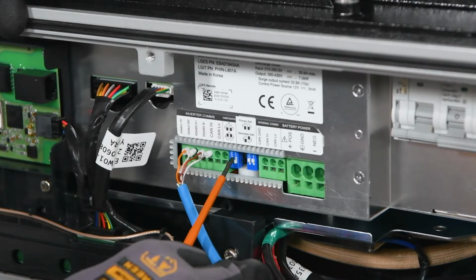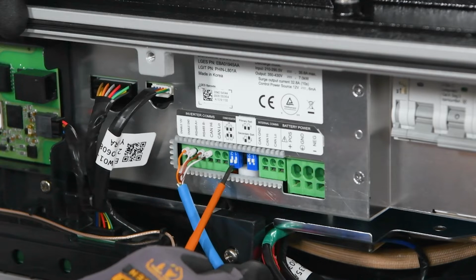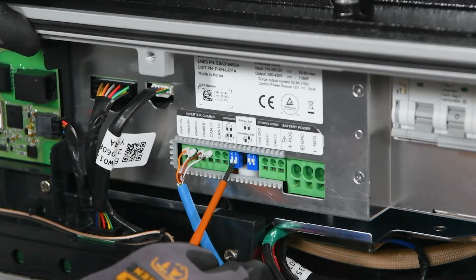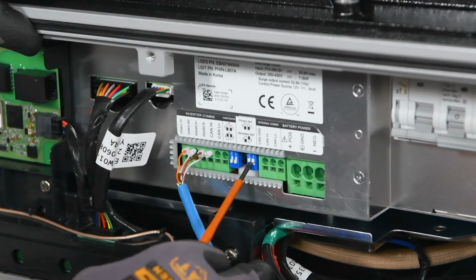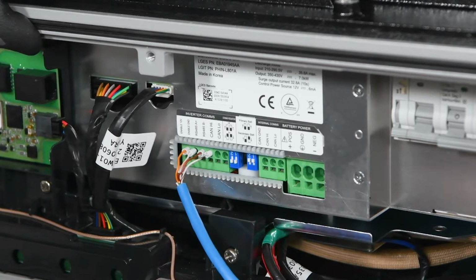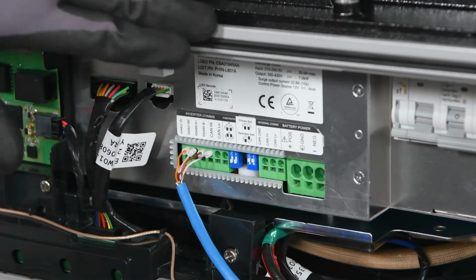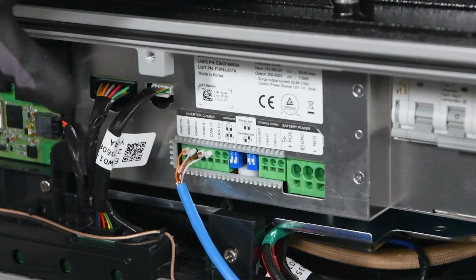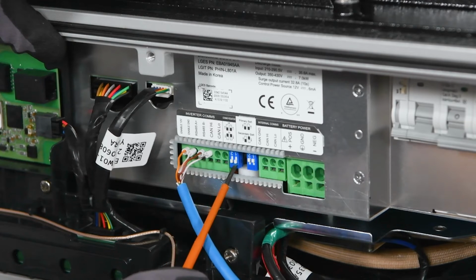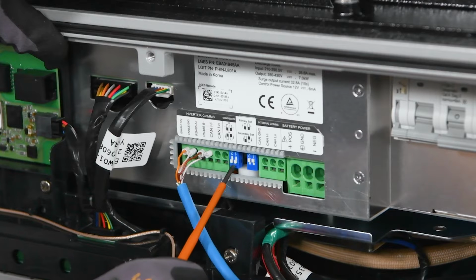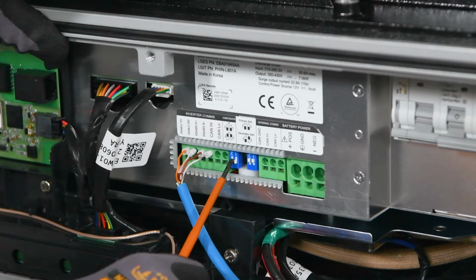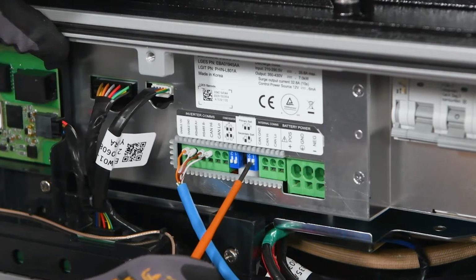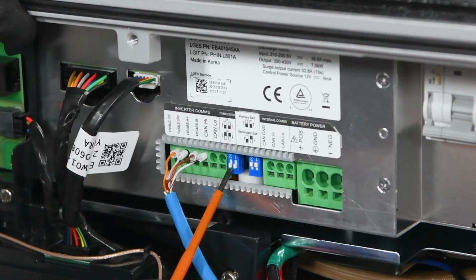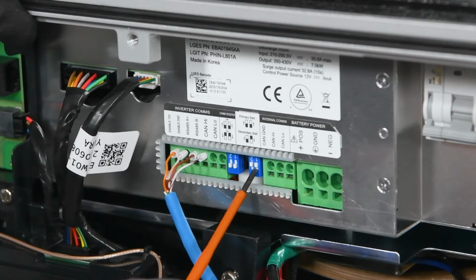But before we move on, we're going to adjust the dip switches for our primary battery. On the left, we have 2 dip switches, and this is going to be our comms resistor dip switches. And on the right is going to be our battery identifier dip switches. When we're setting up our batteries for communication, our primary battery should be the battery furthest from the inverter. For that, we will ensure that our comms resistor is down or in the on position, and the dip switches on the right or our battery identifier are in the up position, as you can see here. So both dip switches on the left are down, and both dip switches on the right are up.